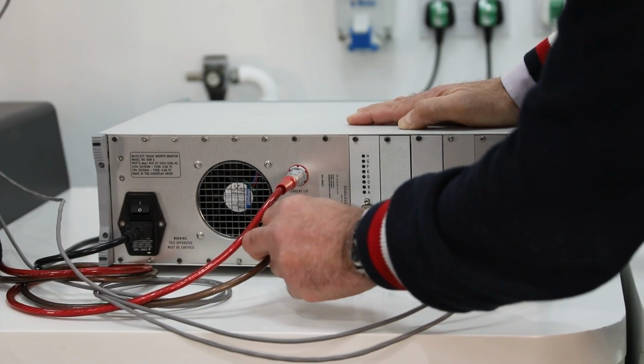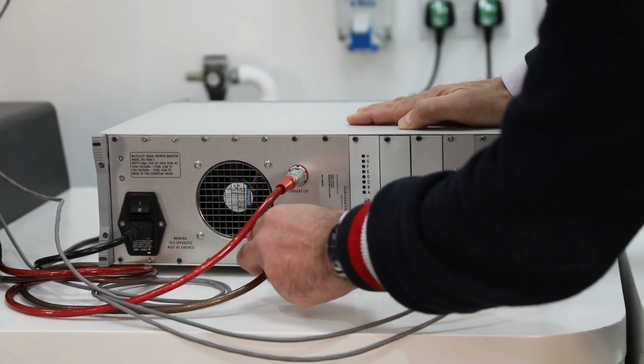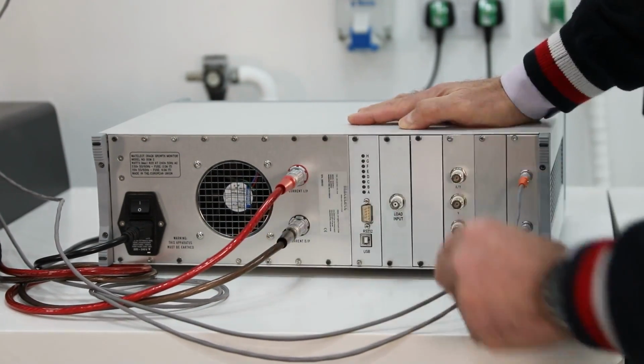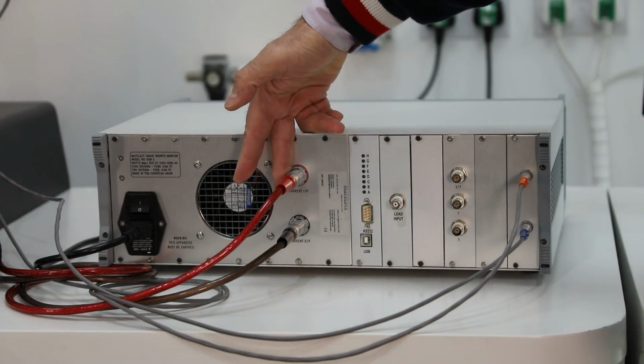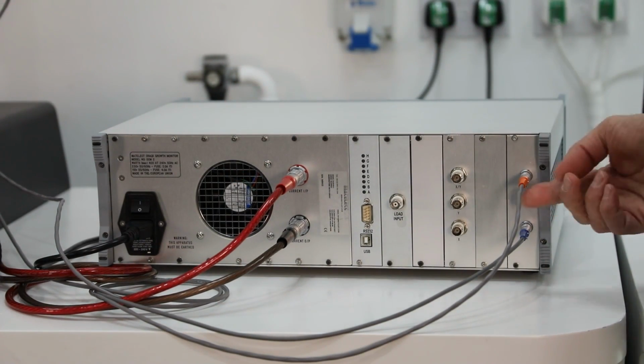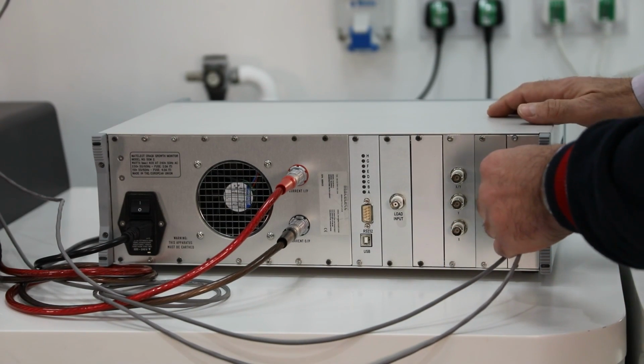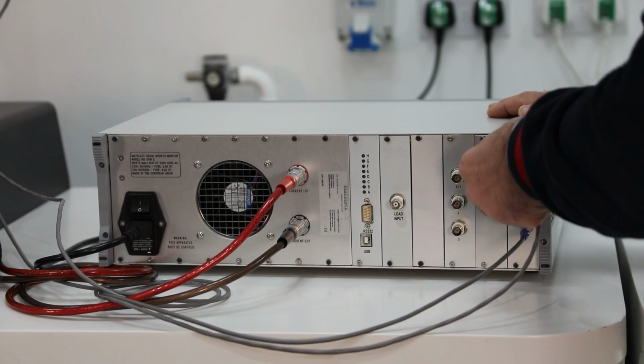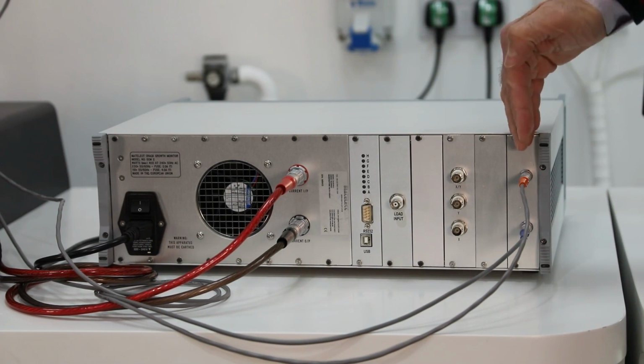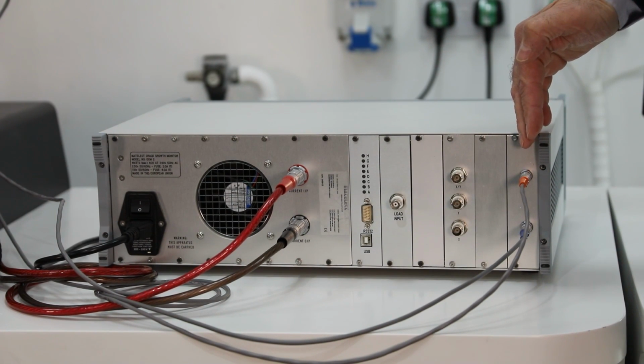You see very thick cables there, necessary to carry the current and not drop too much power along the cables. That's one of the issues with DCPD. The cables can be quite thick. Signal cables are much thinner, and they go into a preamplifier unit on the right-hand side. They're all LEMO connectors, low noise screened cables.